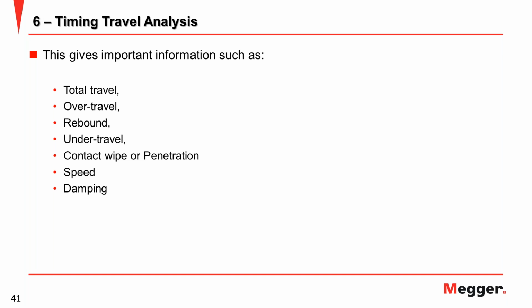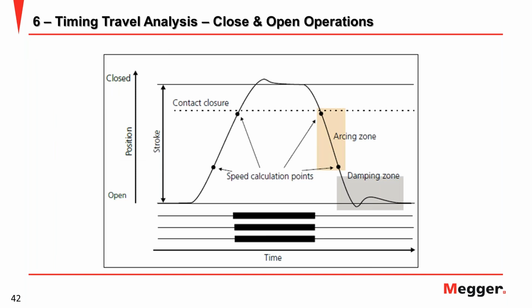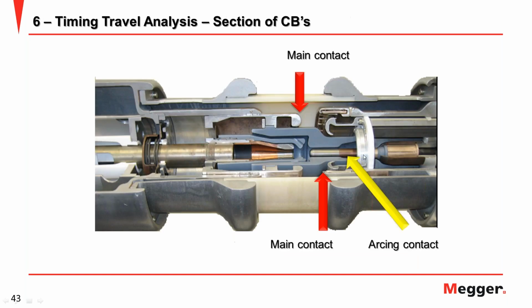What does that mean? If you do the travel and timing analysis, you can find this curve. This curve can give you information about the stroke. Stroke is the maximum distance from the beginning to the end, from this one to this one. This is the stroke value. If there is corrosion or other problems on the mechanical part, maybe the stroke value will be less.